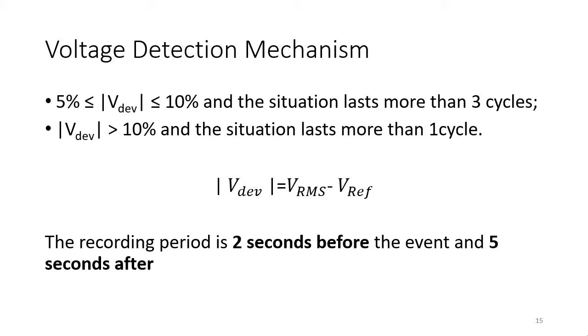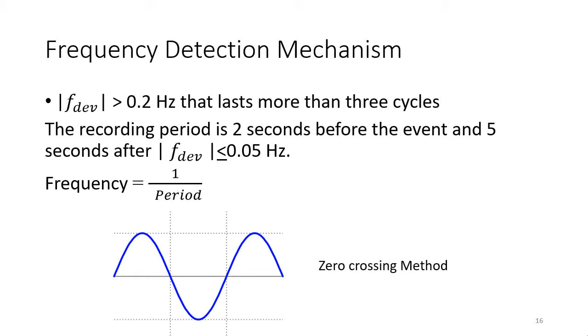For the frequency, as I mentioned earlier, we calculate the frequency based on the voltage data. What we did is we find a period of the voltage data using the zero crossing method, and the frequency is 1 over period. So everybody will understand this part. If the frequency deviation is higher than 0.2 hertz and lasts more than 3 cycles, the system is going to start recording until the deviation is less than 0.05 hertz. This is the frequency detection mechanism.